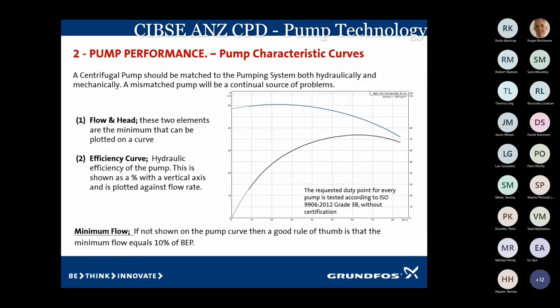Moving on to the pump performance curve. The pump performance curve is data that the manufacturer produces, and the performance curve is determined by the diameter of the impeller and the motor speed.